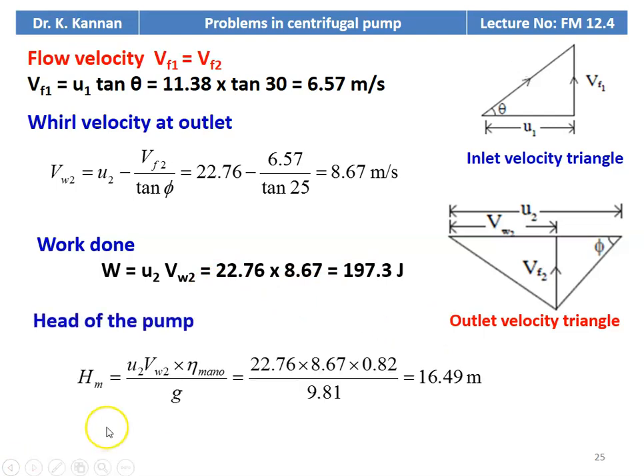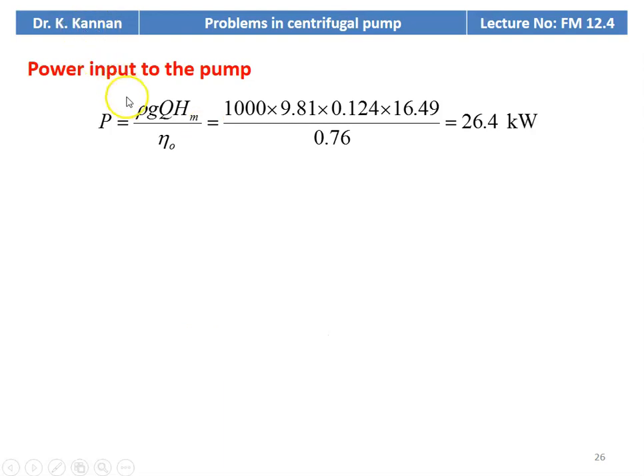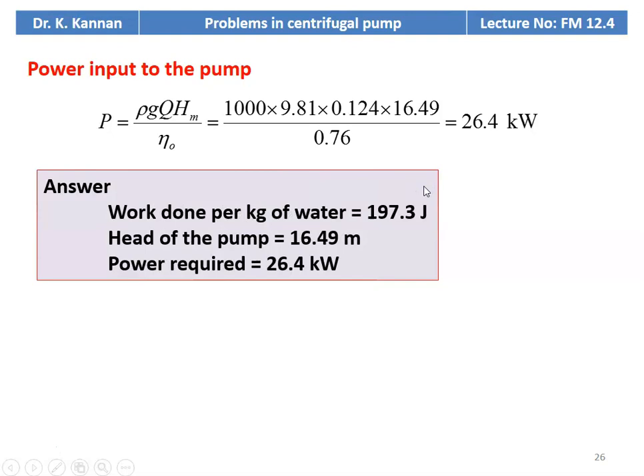The manometric head from the definition of manometric efficiency: manometric head equal to U2 VW2 into manometric efficiency divided by g, substituting: 22.76 into 8.67 into 0.82 divided by 9.81 equal to 16.49 meter. Discharge Q equal to pi D2 B2 into VF2: 3.14 into 0.3 into 0.02 into 6.57 equal to 0.124 meter cube per second. Power input P equal to rho g Q Hm divided by overall efficiency: 1000 into 9.81 into 0.124 into 16.49 divided by 0.76 equal to 26.4 kilowatts. Answers: work done 197.3 J/kg, head 16.49 m, power 26.4 kW.